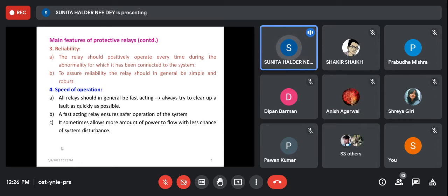But sometimes a transient condition appears in the transmission line, which is very instant. After some time it goes, like a bird falling on a transmission line or a tree branch falling on the transmission line. In that case, the abnormality comes for a very short time, and it creates some transient in the system. But when it goes, the system becomes normal. But if the relay is so sensitive and its speed of operation is so high, then it will operate within that transient condition. So then what will happen? There will be unnecessary tripping of the system that was not required, because that transient will die down automatically. So high speed of operation is also not preferred sometimes. High speed of operation may be applied for a generator but not for a transmission line in that way.